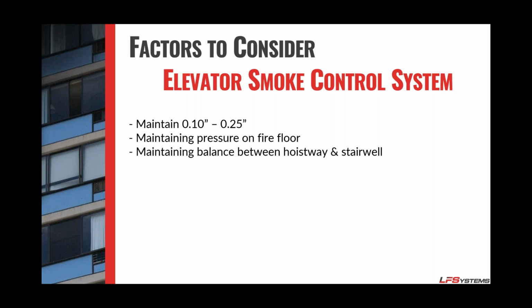You obviously still have to maintain your 0.1 to 0.25. You have to maintain pressure on the fire floor, right? That's the floor we really want to make sure that we're pushing back against the smoke. And then you have to maintain balance between your hoistway and your stairwell. So you may make your hoistways safe for either the first responders or the evacuation plan, but how does that affect your stairwell?